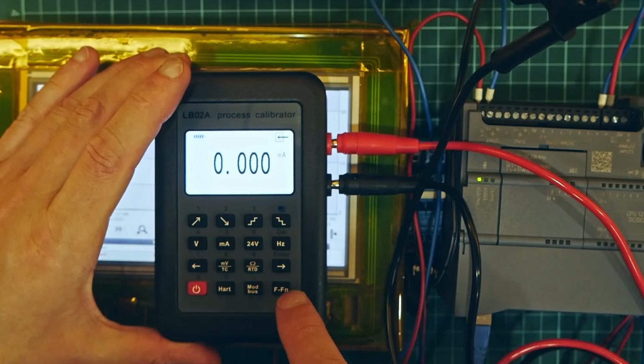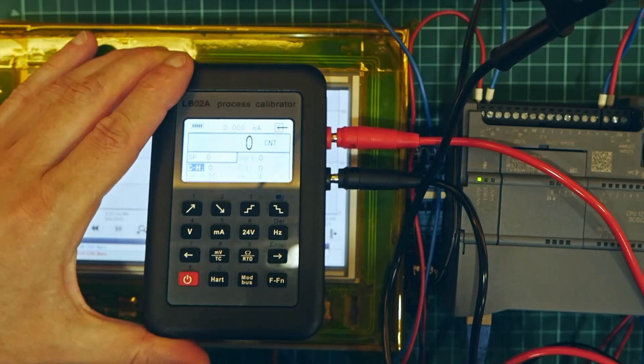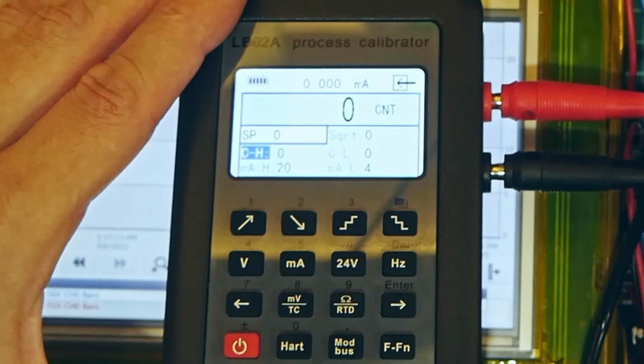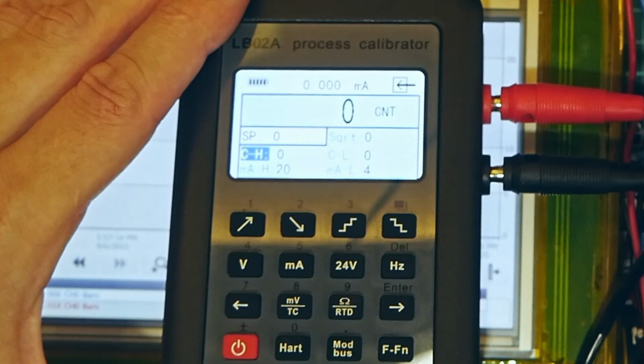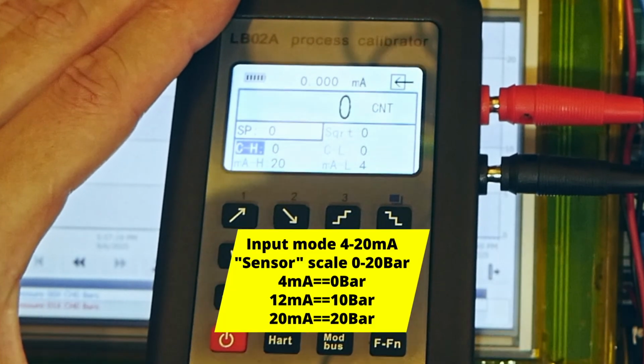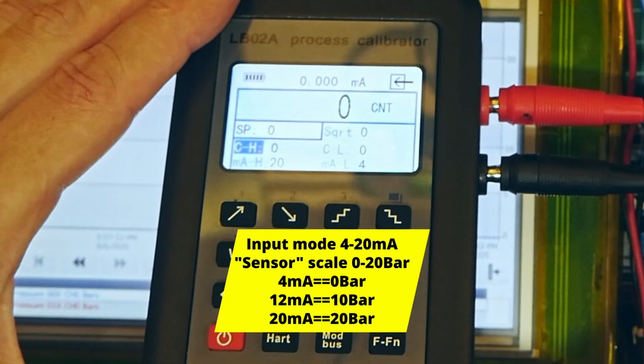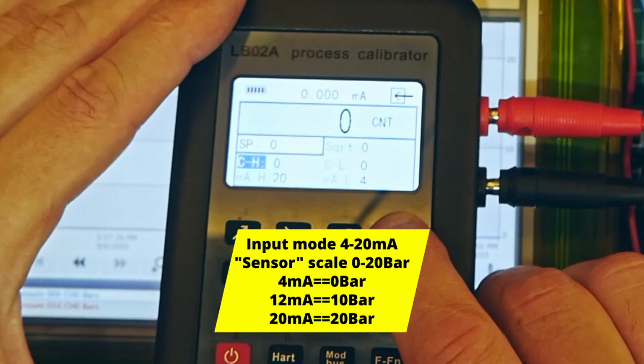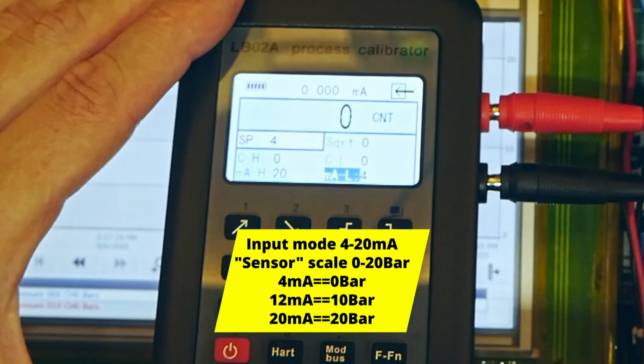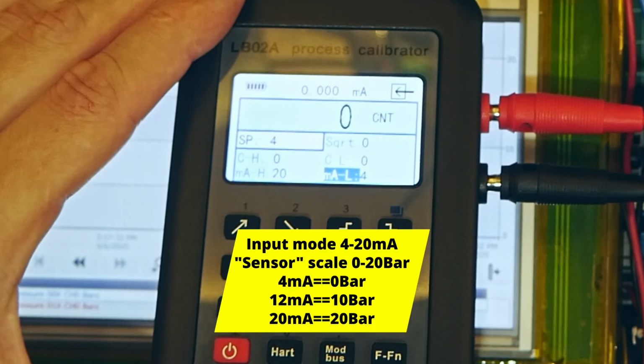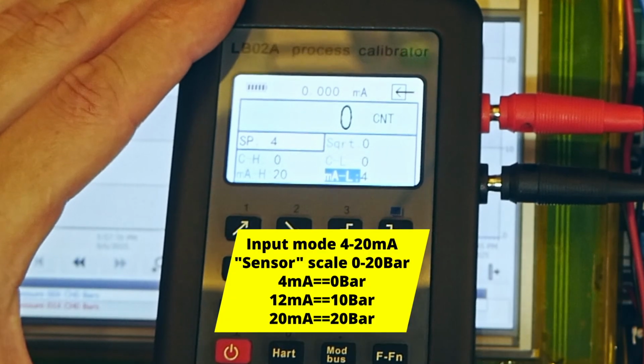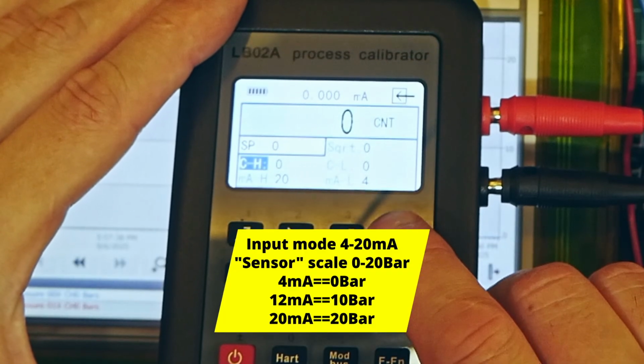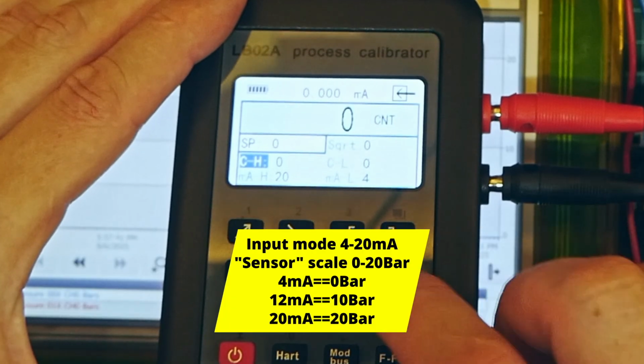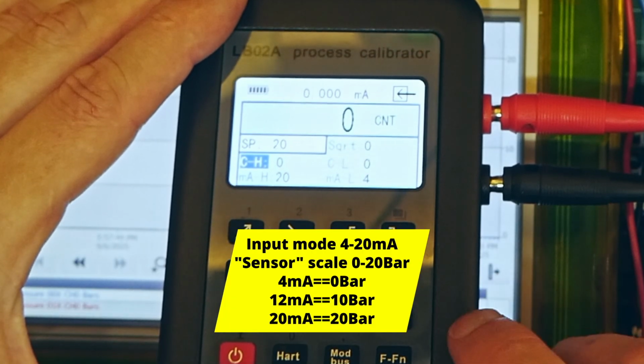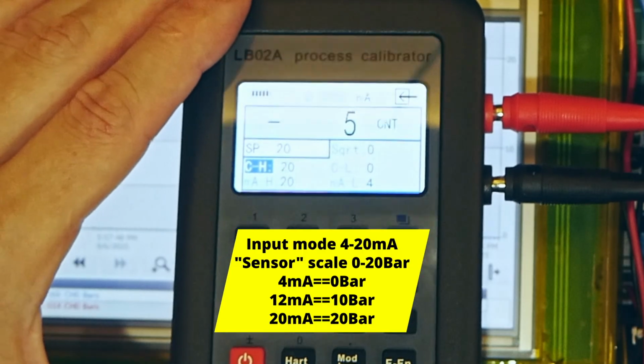And if you press the function button, in input mode, as in voltage mode, everything is the same, we can enter the scale. Just right now the scale is not from 0 to 10 volts, but from 4 milliamperes to 20 milliamperes. So 4 milliamperes will be 0, and 20 milliamperes, let's set also to, let's say, 20 bars. Enter, and yeah, we can simulate that again.